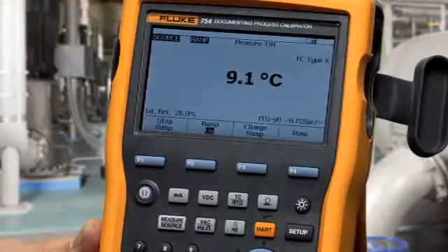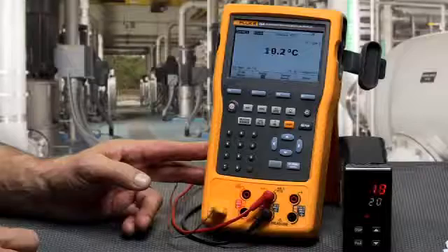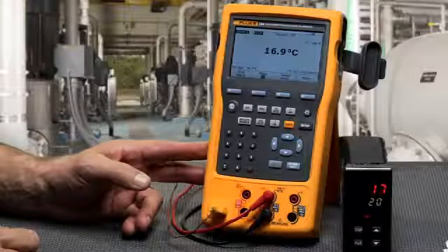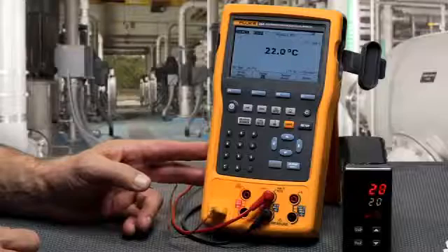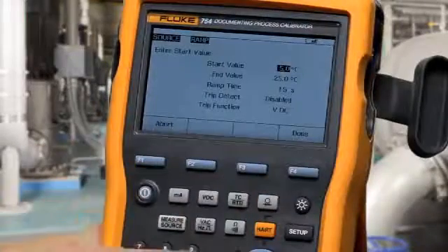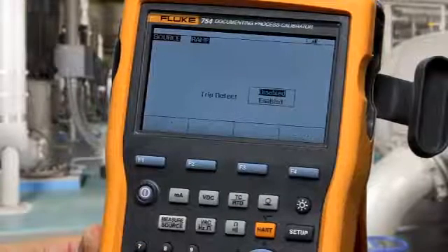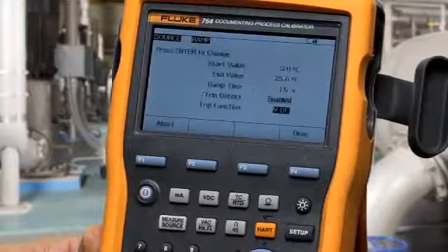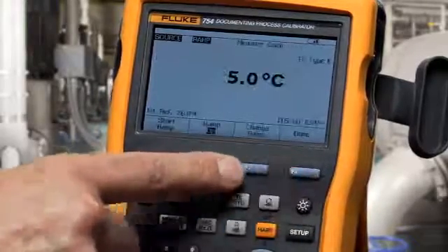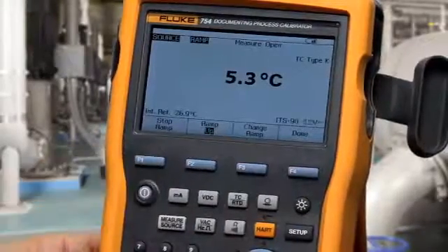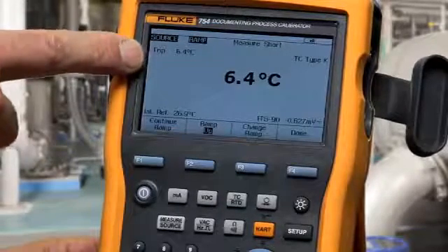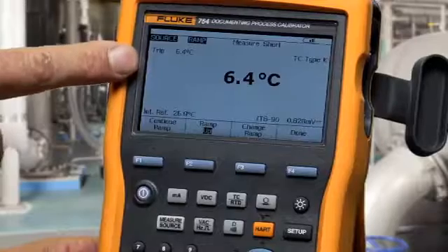To do a ramp with trip detect, the calibrator will ramp the temperature and freeze on the temperature at which it measures a contact state change on the resistance measurement terminals of the calibrator. Select change ramp, enable trip detect, select continuity, and press start ramp, and the calibrator will freeze the temperature that it measures the contact's change state. In this case, 6.4 degrees C.